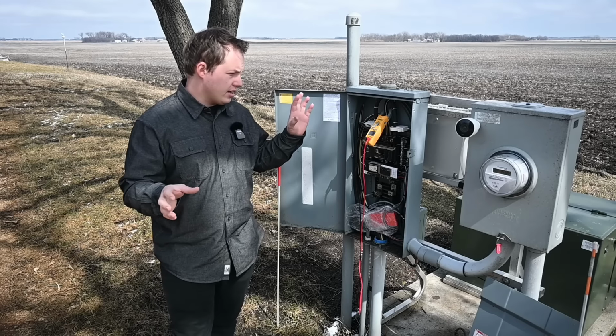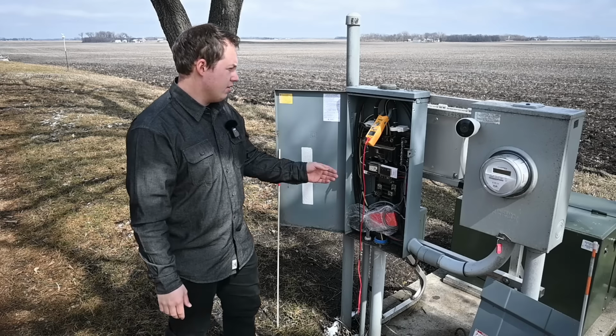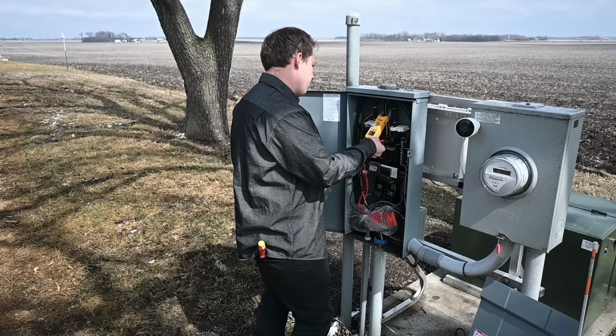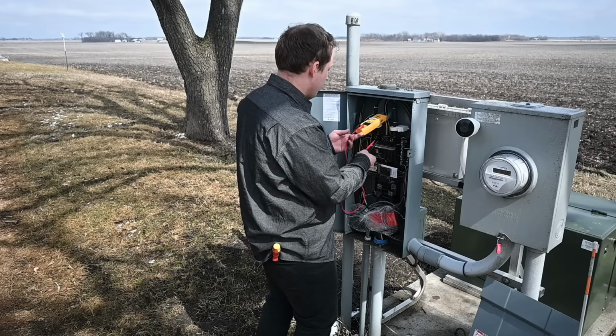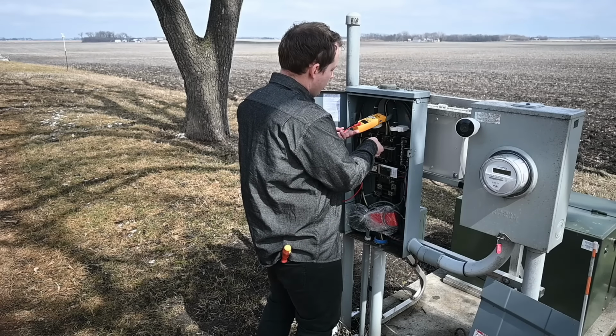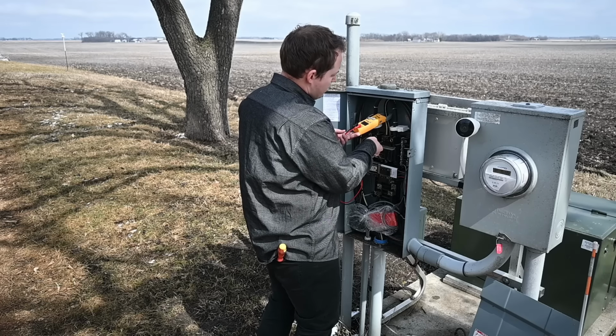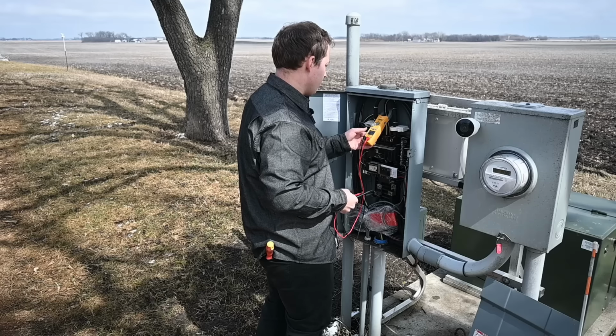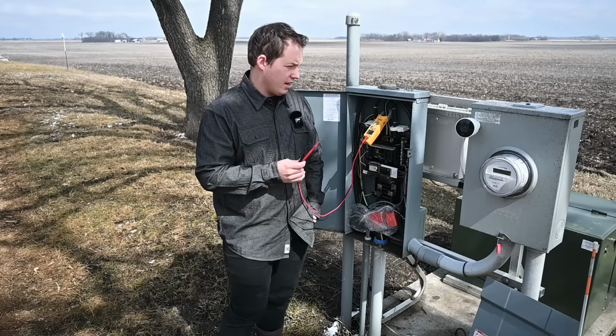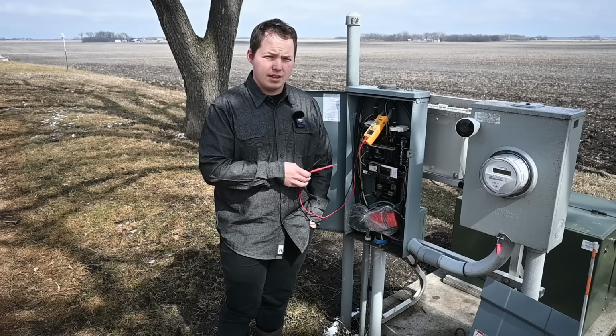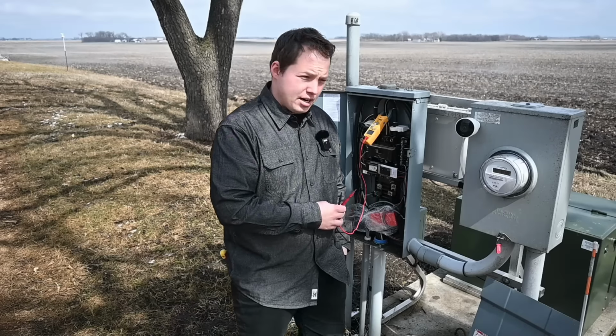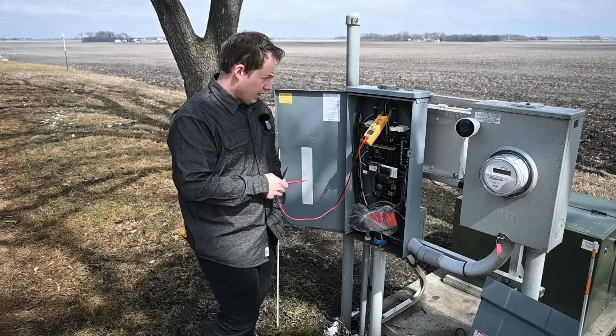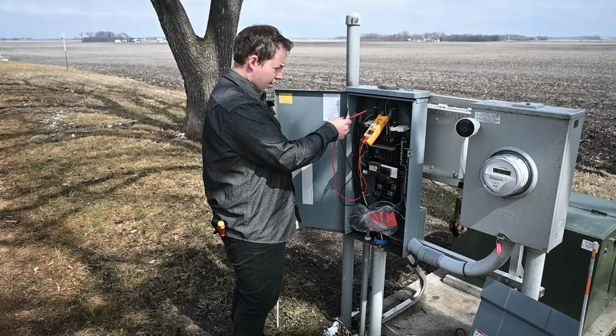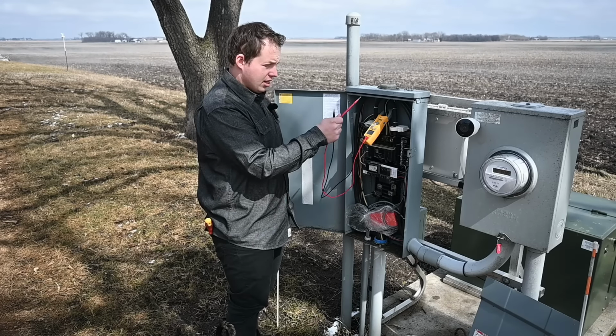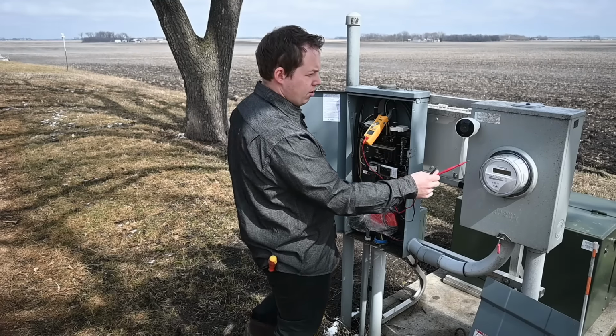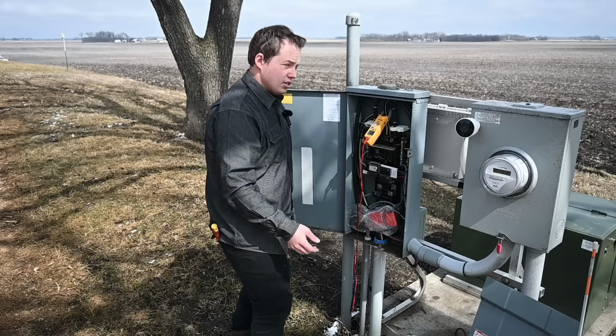So right now that neutral wire is at 0.36 amps, so still a pretty good amount of current. 125.6 volts on one leg, reference to neutral, and 125.6 volts reference to neutral on the other leg. So we are very consistent there. So the good news about this is that it doesn't seem like my electric meter is counting this power usage. I'd have to put a time lapse on it to make sure that it doesn't move. But as far as I know, it only monitors the usage on the two hot legs and not the power usage on the neutral. But I could be incorrect. Correct me in the comments down below if I'm wrong about that. But I'm pretty sure that's how these meters work, is they just measure the two hot legs.